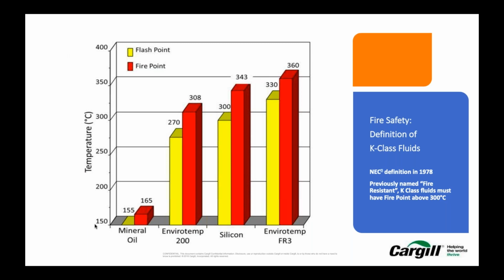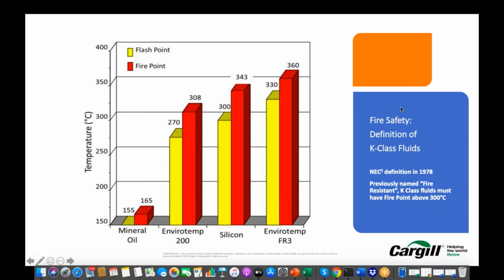Then we deep dive into their classifications based on fire point and flash point. The fluids shown on the slide come from dielectric applications: silicone fluid, synthetic ester, natural ester, and conventional mineral oil. The best mineral oil available today, be it imported or as per IEC 60296, has a fire point in the range of 160 or 155 degrees C. And the other fluids, like synthetic ester, have a fire point close to 310 to 350 degrees C. Silicone fluid has 340, and natural ester has the highest, which is 360 degrees C.